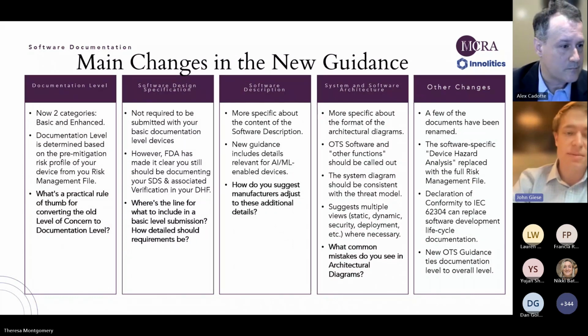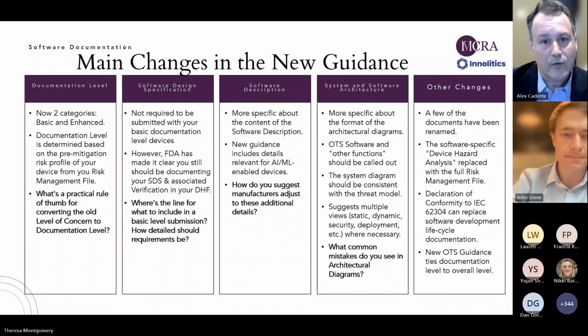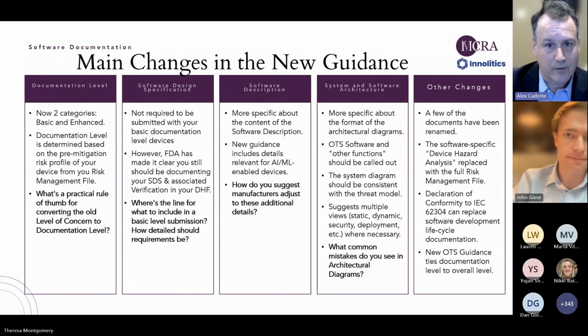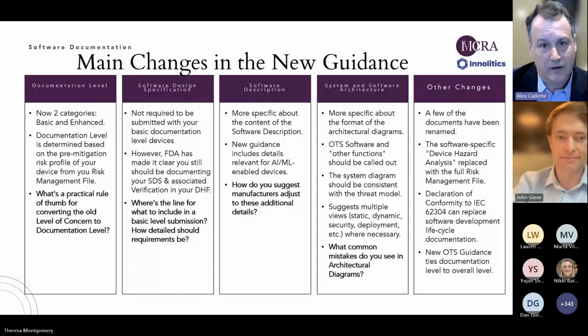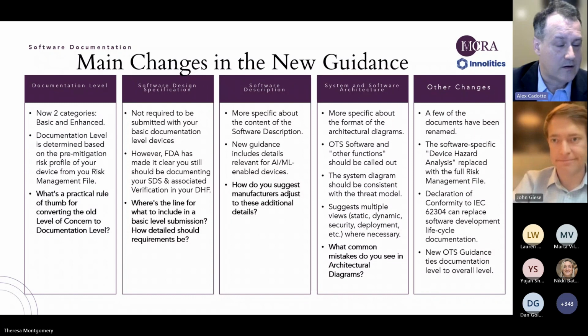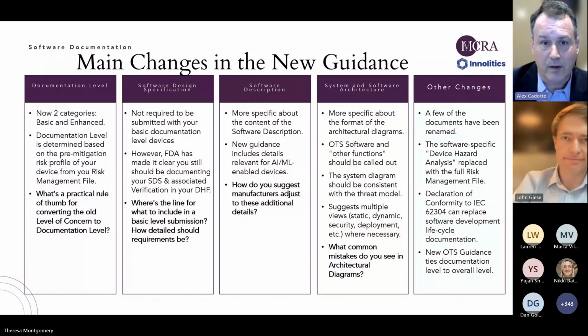Anyway, Alex, what would you say is a practical rule of thumb for converting between the old level of concern for companies with existing devices and existing documentation to the new documentation level? So often in 510K summaries, you'll likely find where the level of concern was documented for older devices. Generally speaking, minor and moderate are going to pretty much map to basic, and major is going to map to enhanced. And there is some gray area there because FDA left room for basically the risk of your device kind of informing what the documentation level is. But generally speaking, you should be able to use that precedence that you see, with some exceptions, to be able to inform what the new documentation level would be.